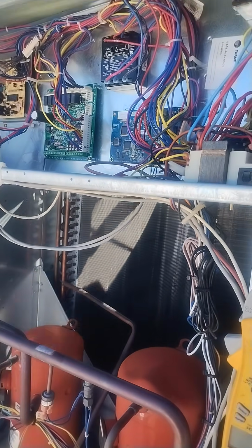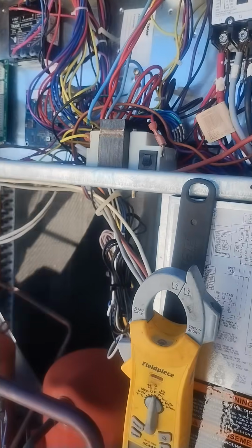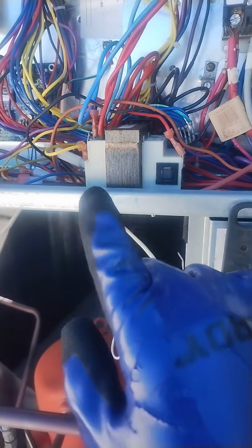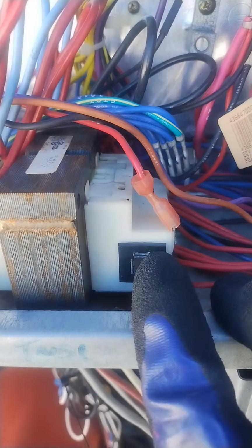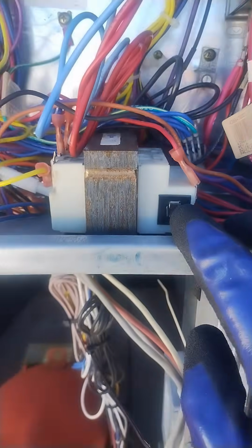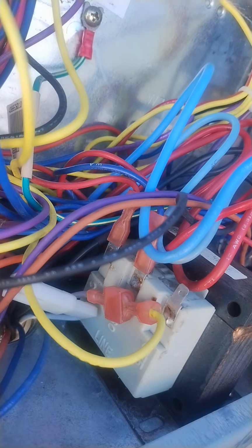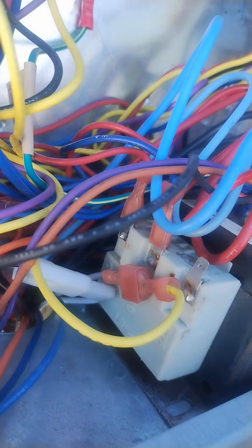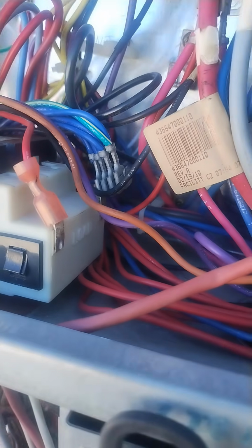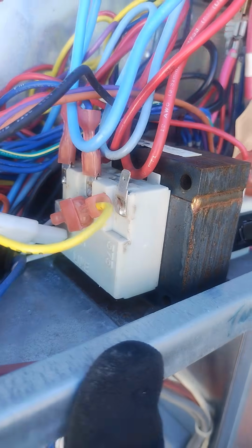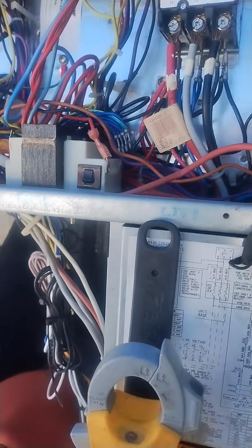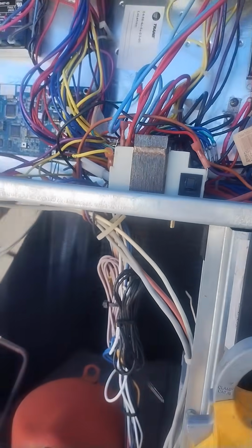So what's the next thing you do, guys? I go to the source of the 24 volts. The source of the 24 volts is this transformer, step down transformer. Looks like it's tripped. It's defective. It's not fully resetting. So I verified that I'm having 480 volts on the line side. I got my 480 on the line side, but then on the load side, which is the step down side, I'm supposed to have 24 volts. And I have nothing between, when I put my meter here and there on these two terminals, I have no 24 volts. And this transformer is definitely getting the 480 volts. So we're going to get the transformer replaced, and then we'll be able to check the unit.